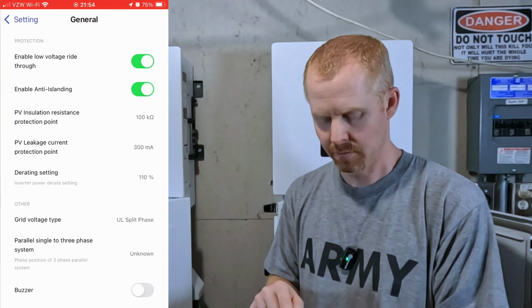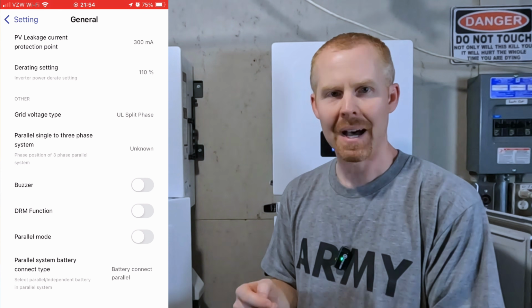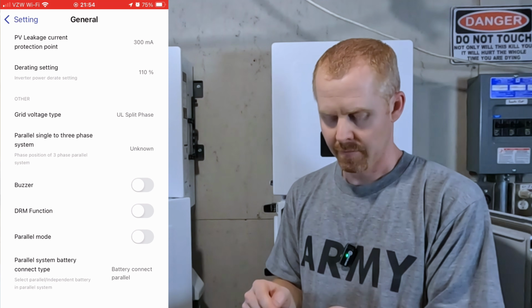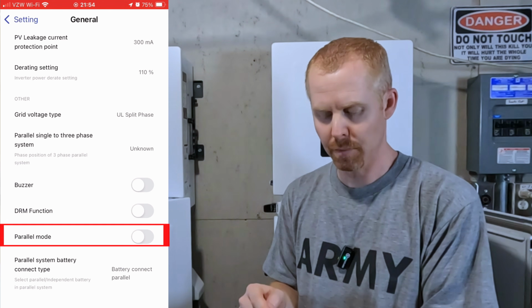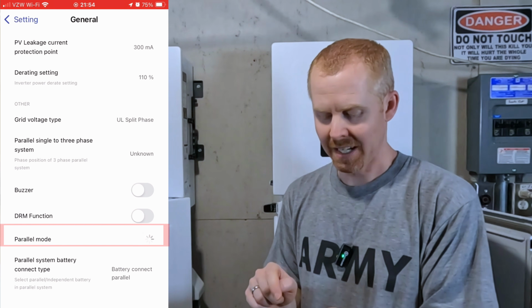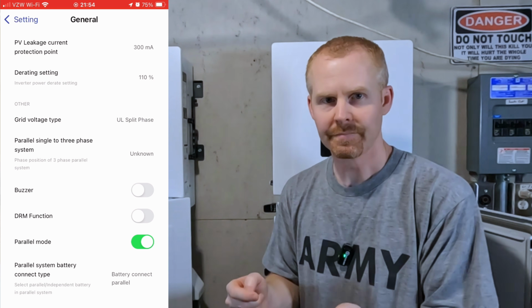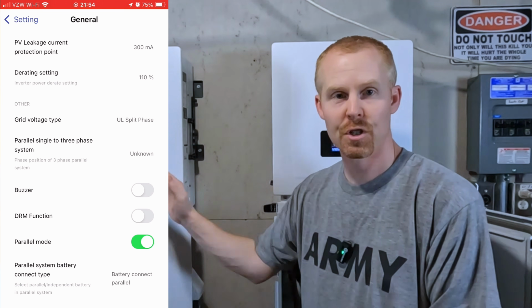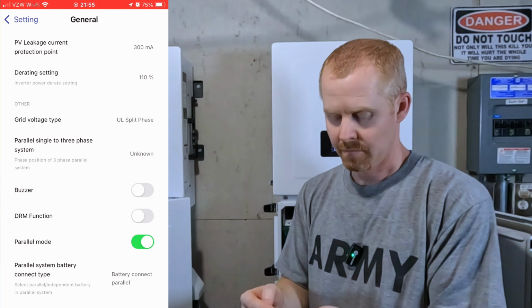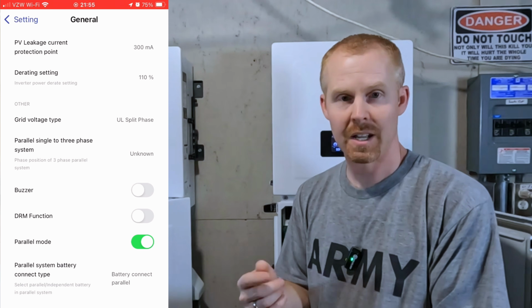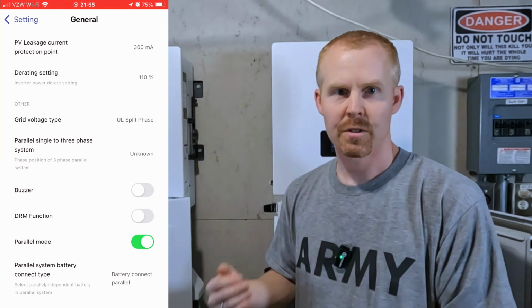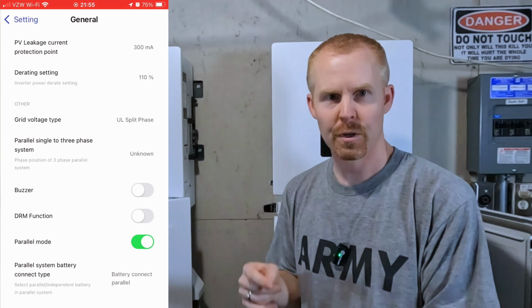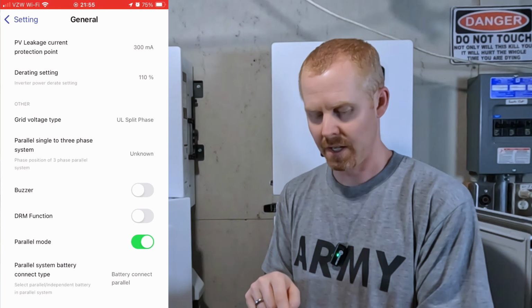Go to general, and then down at the bottom of general, second option from the bottom says parallel mode. So we're going to tick that, parallel mode. That's going to start the communication between the two inverters. By default, it'll say battery connect parallel because you're using a parallel battery bank. If you're using a split bank, you would change that right here.